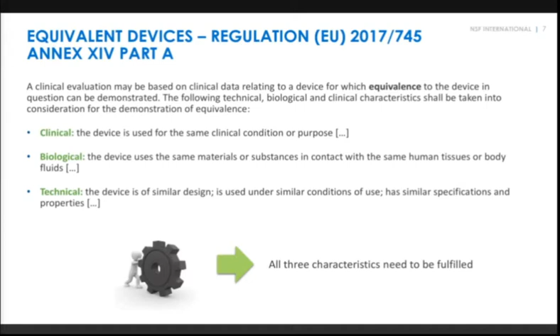years. The biological and clinical characteristics, such as the same clinical condition or purpose, same materials or substances in contact with the same human tissue or body fluids, should be the same between the device under evaluation and the equivalent device, whereas the technical characteristics should be similar. So the question is, what does similar mean? So there's also a definition which is written by the regulation, and the characteristics shall be similar to the extent that there would be no clinically significant difference in the safety and clinical performance of the device.